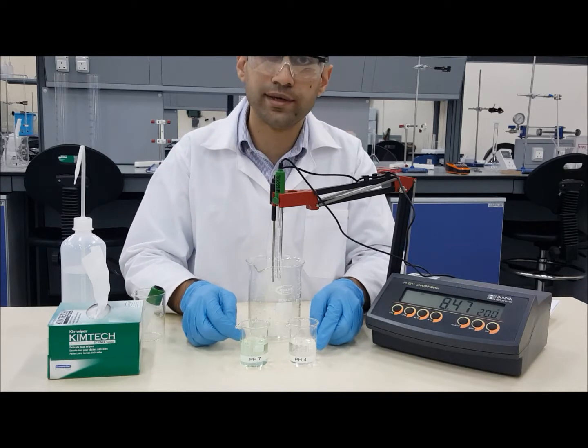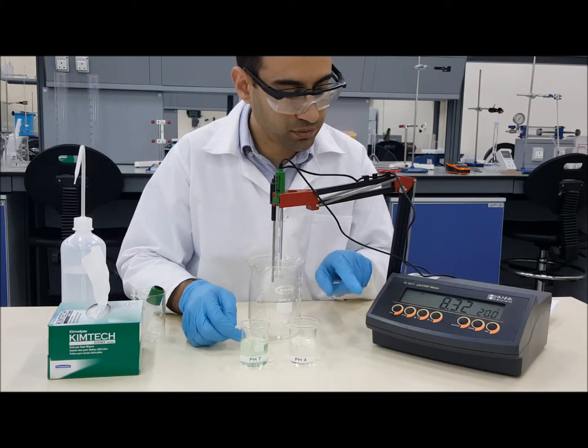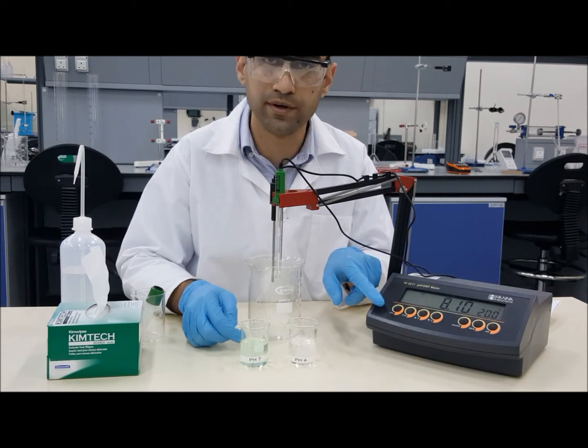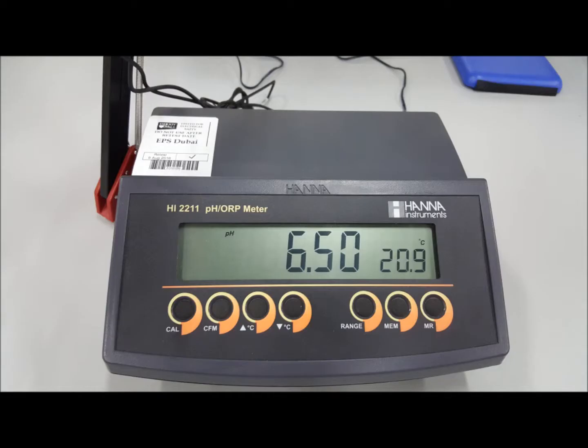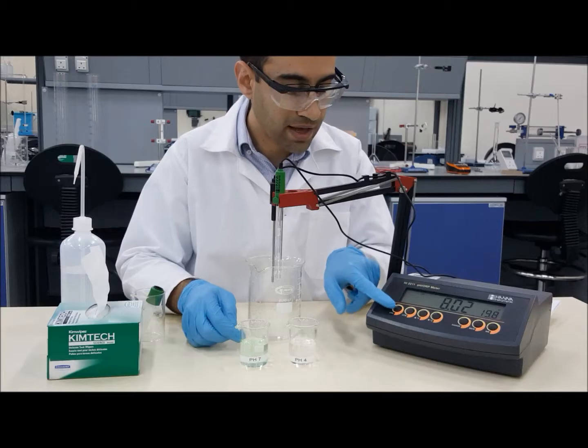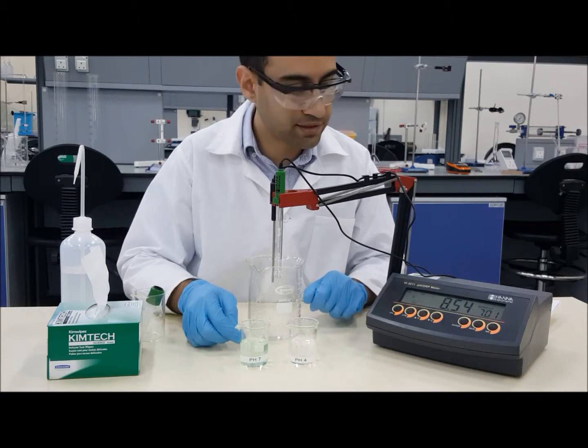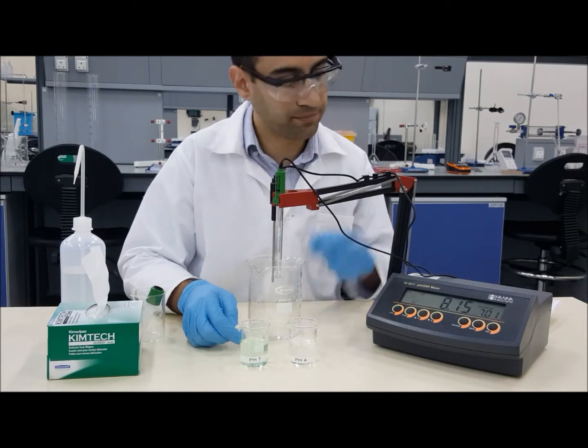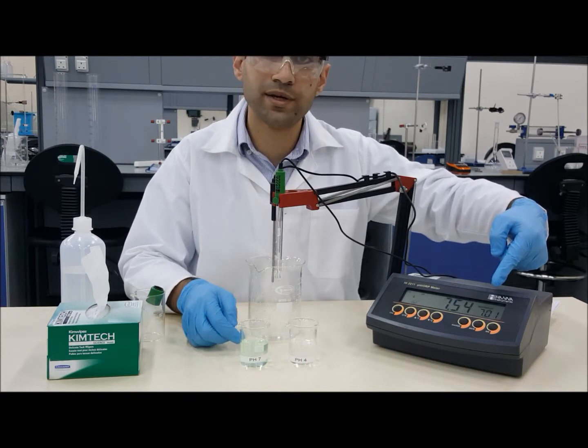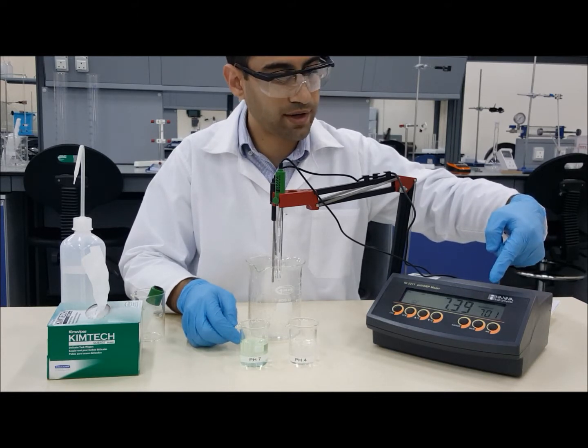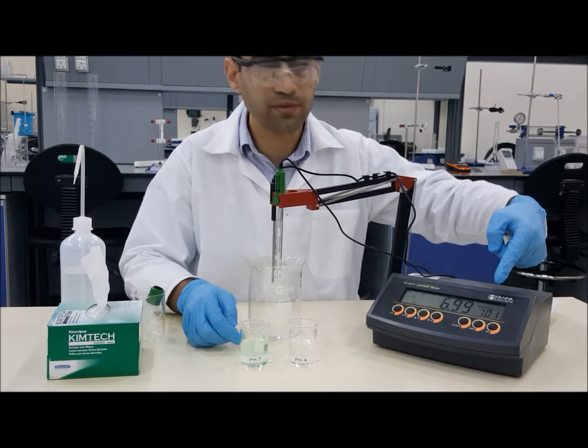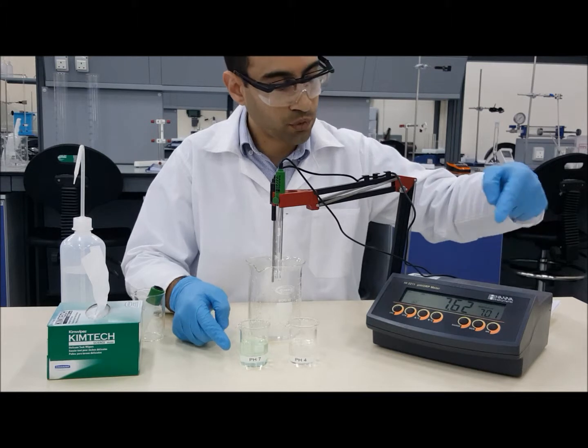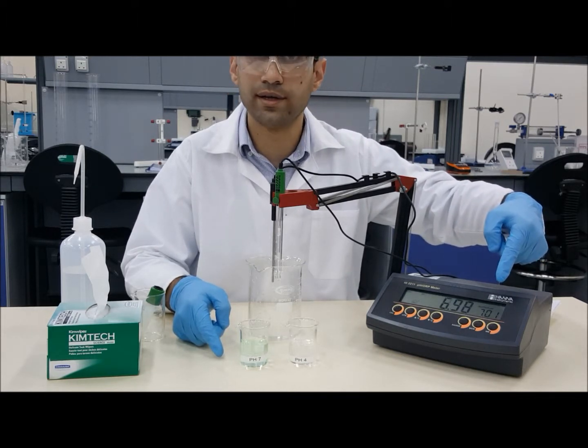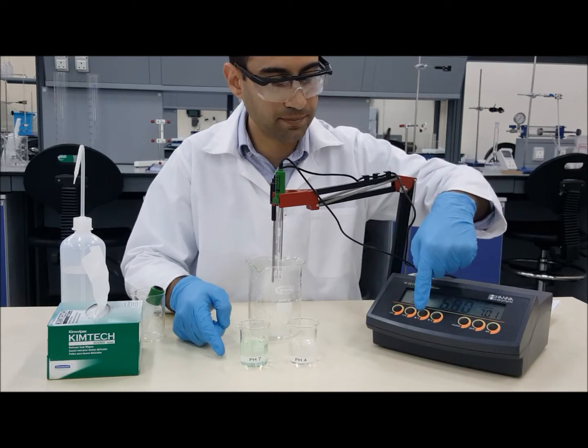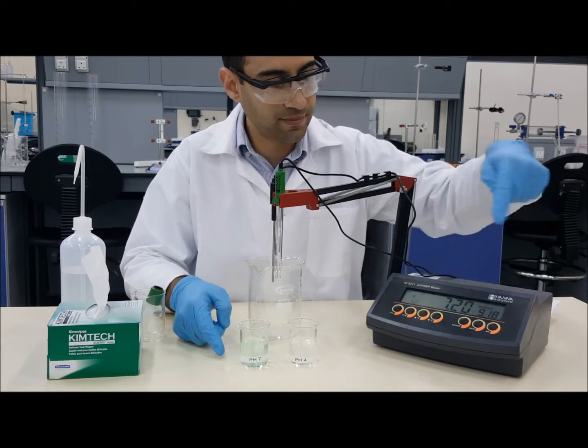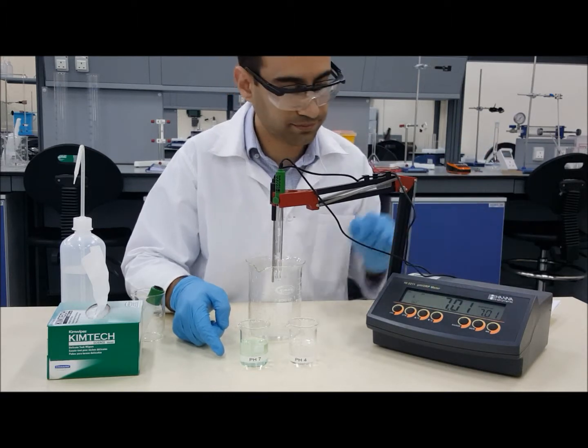In order to get into the calibration procedure, we will need to press on the calibration button, the first one, CAL, is for calibration. As we press, we will get some information on the screen which we will need to follow. At the corner there, we will get the expected value for the buffer solution. Right now we are getting 7.01, so we can use pH 7 for that purpose. We can change that value, depending on the calibration we are taking, by using these up and down buttons. So changing this up and down will change the buffer solution up and down.